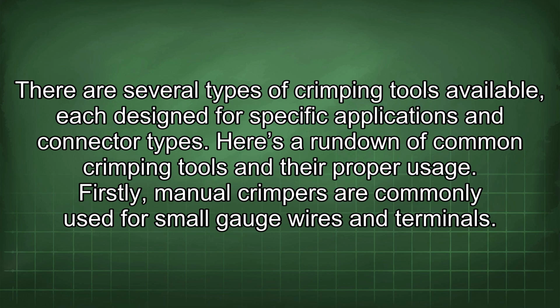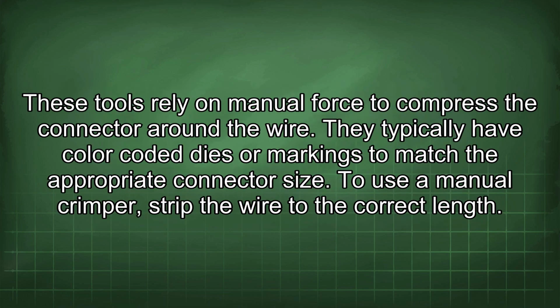Firstly, manual crimpers are commonly used for small gauge wires and terminals. These tools rely on manual force to compress the connector around the wire. They typically have color-coded dies or markings to match the appropriate connector size.